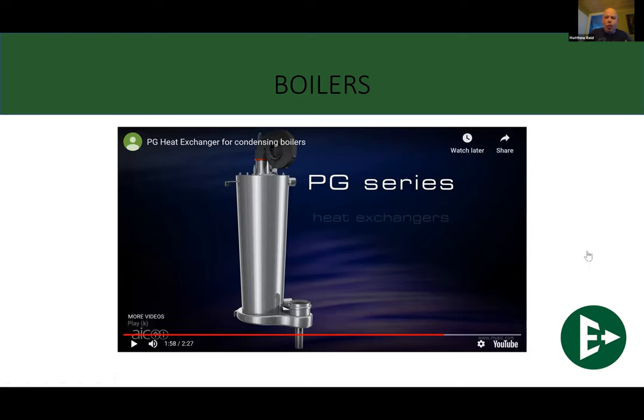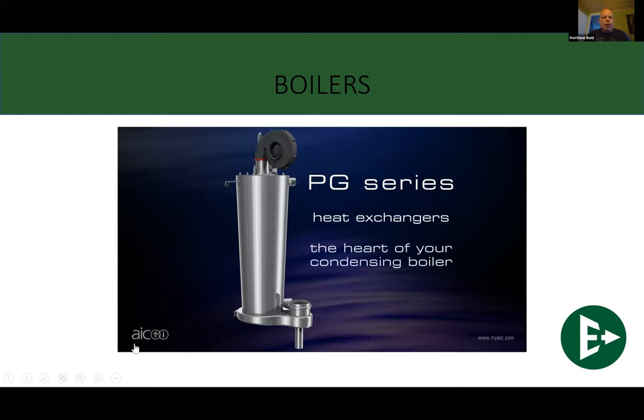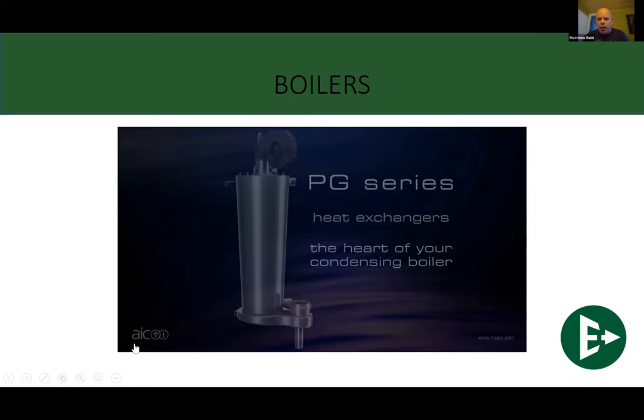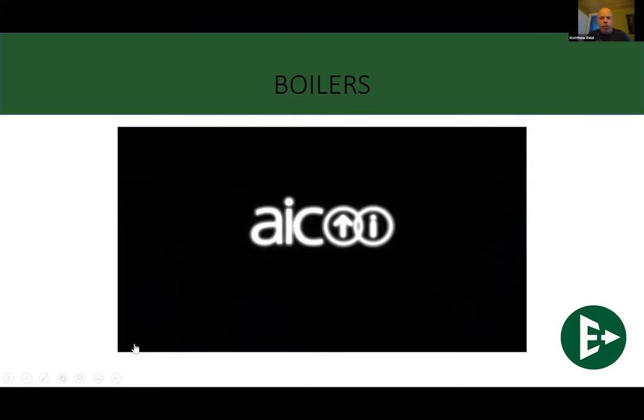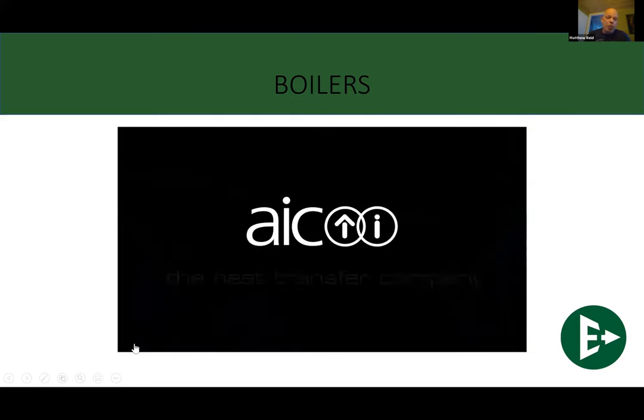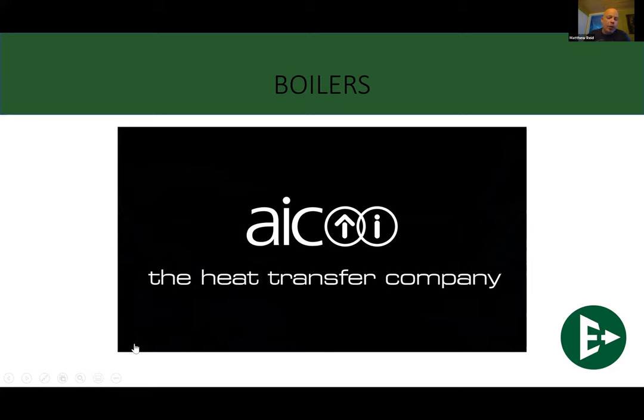So it does have its features. It is a bit more complicated with regards to how to take it apart and clean it, but it is usually quite efficient, and the super low head loss through these makes it so you can do some pretty interesting piping schematics. Usually with these high efficiency boilers, we have to do primary-secondary piping. With a fire tube, you can actually get away with just a standard in-out system, depending on the system overview as a whole. But that's going to be up to you and me as we sit there and design an overview for a system.